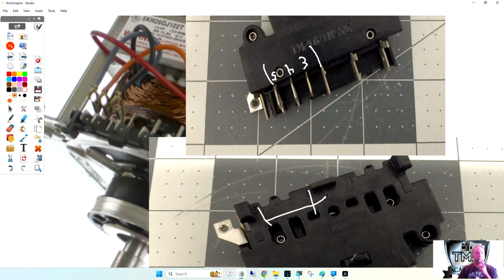There's one more thing you need to do to check 5 and 6. What do you need to do? We unplug it, get down to the motor, find 5 and 6, put our meter on it, and our meter says the switch is open. Is that good or bad?